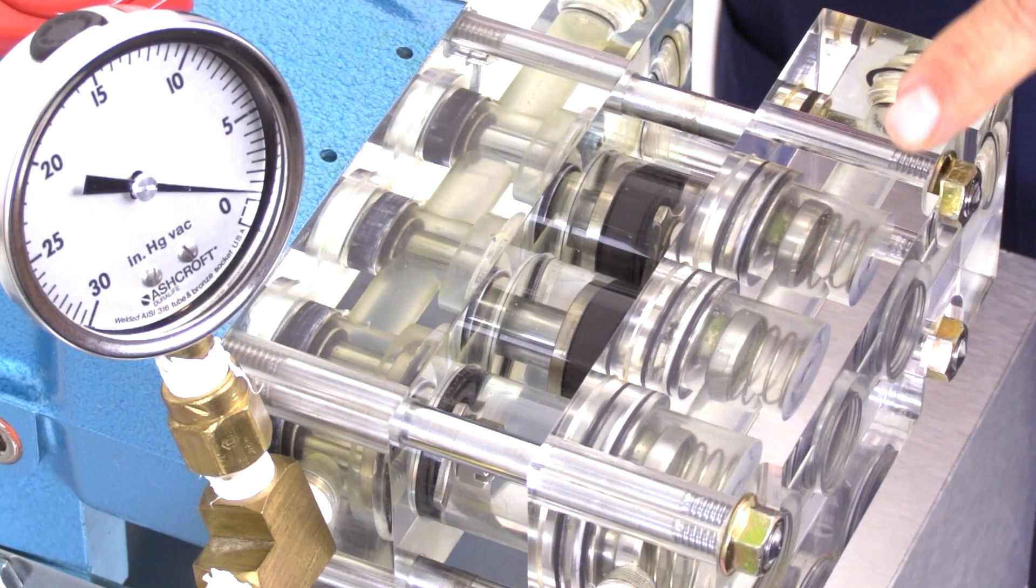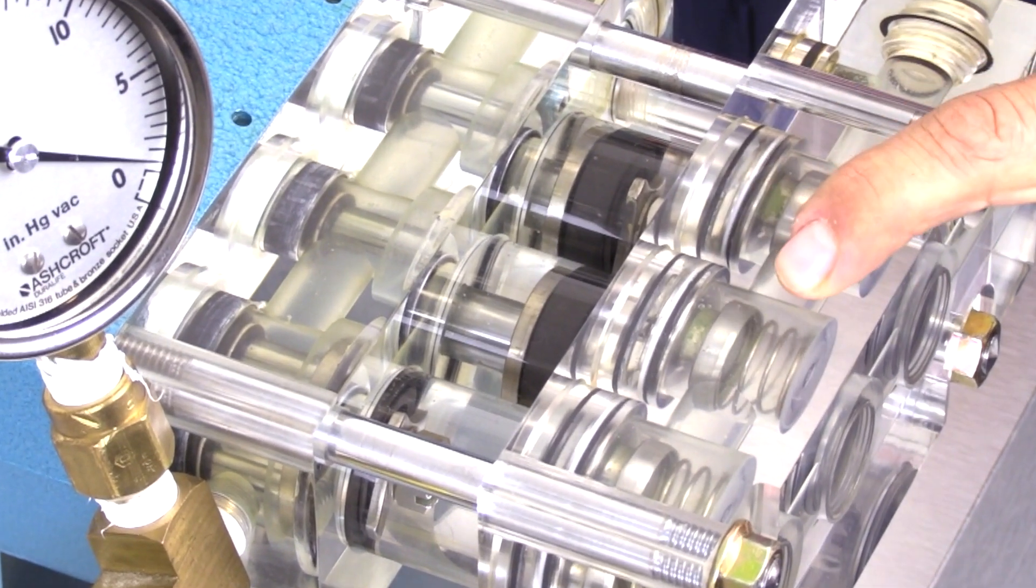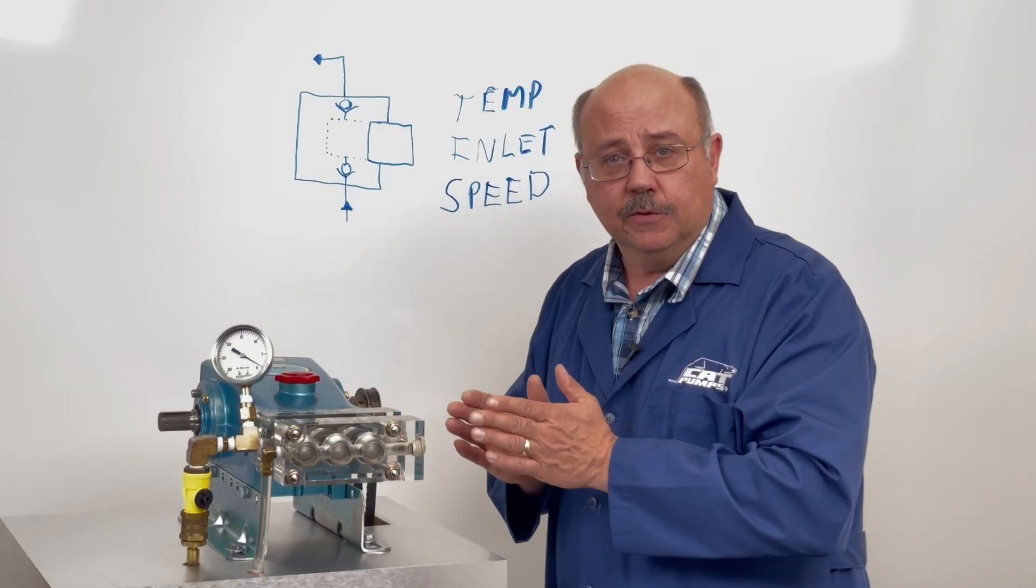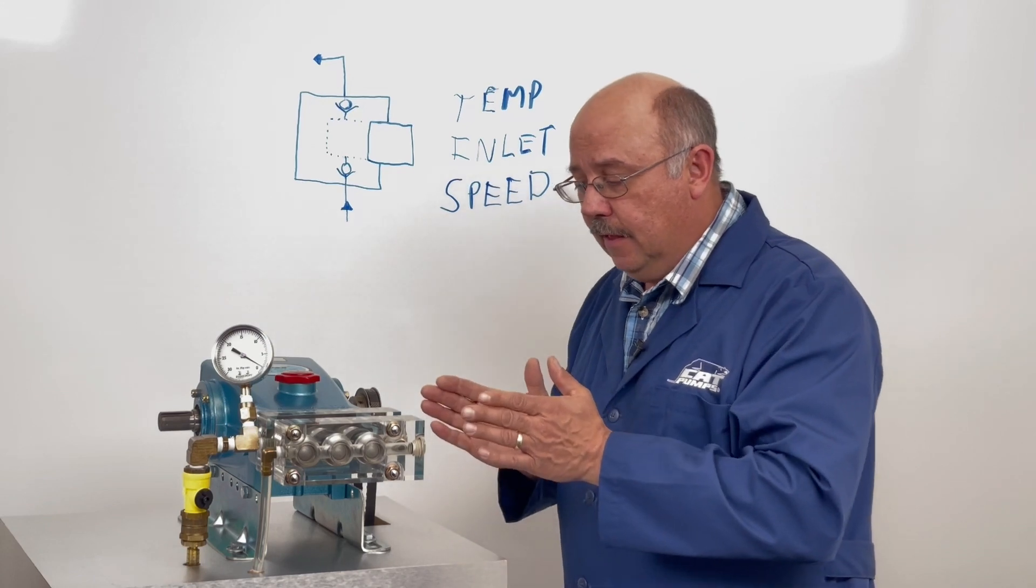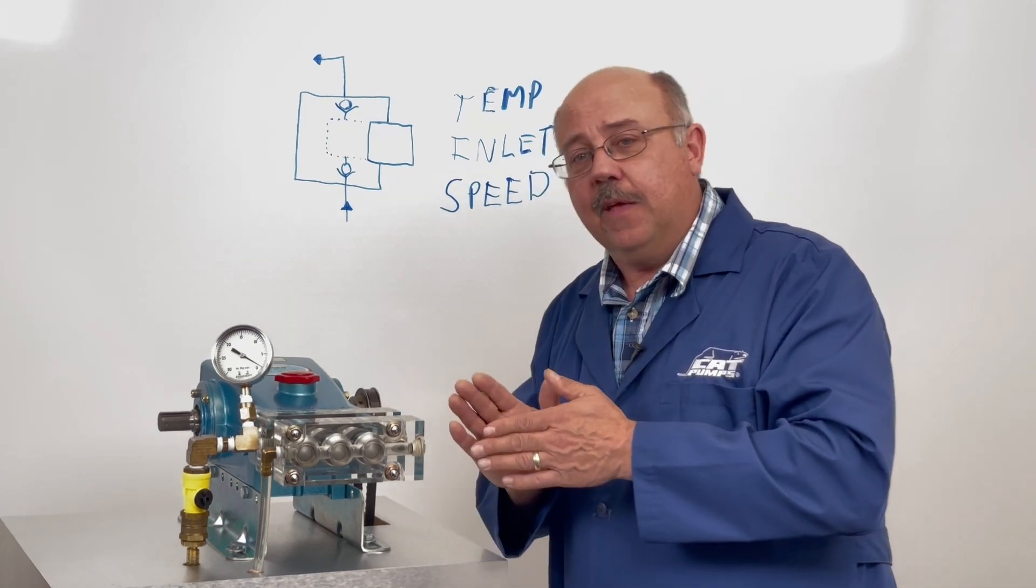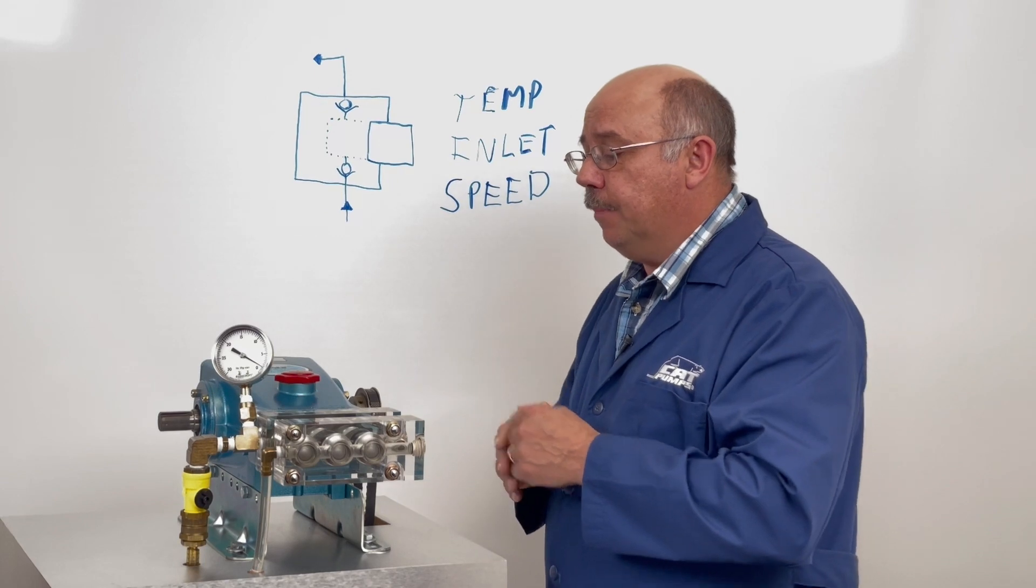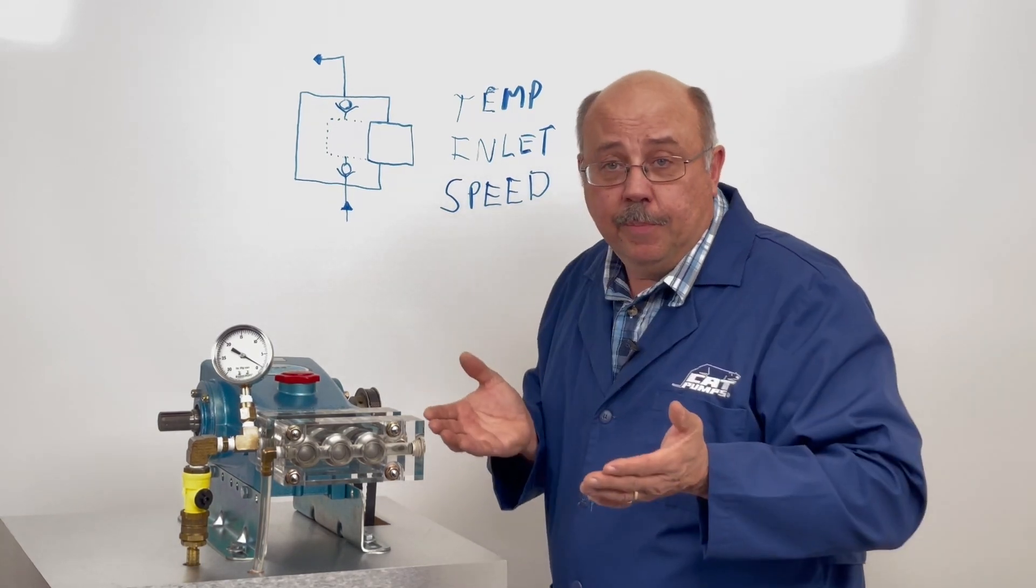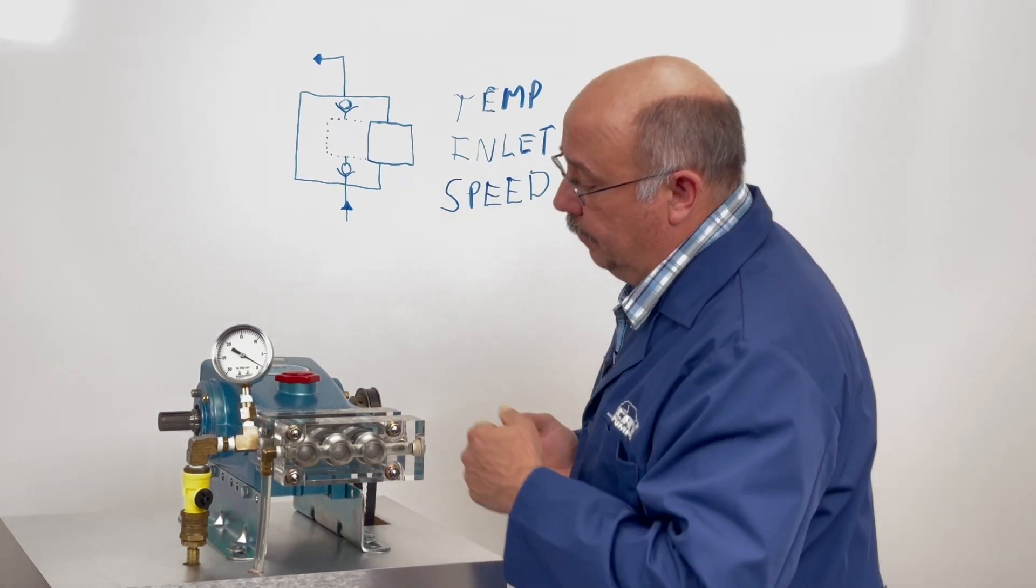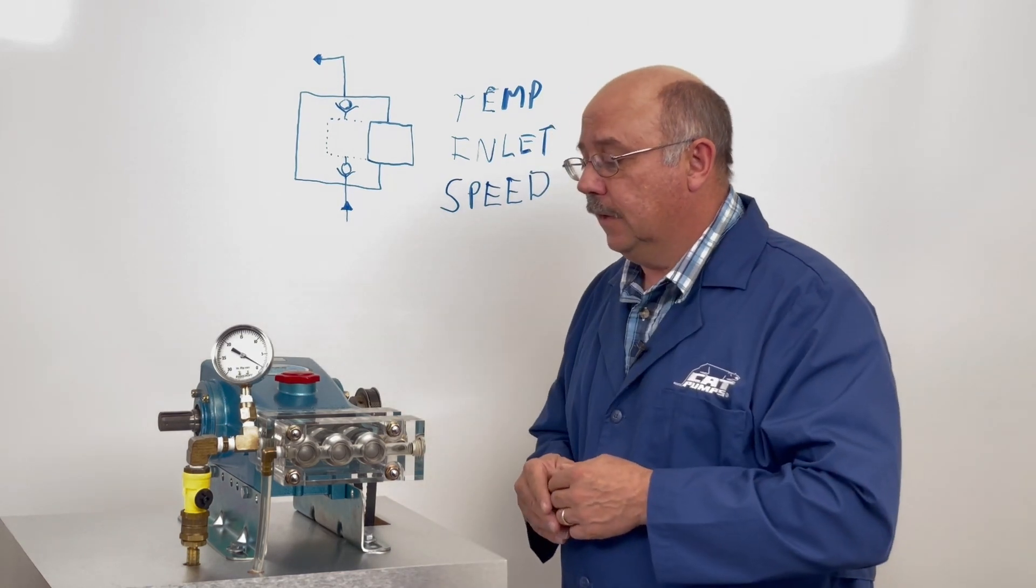And then there's a discharge valve assembly with a spring and a valve that's held closed by that spring. And then during the forward stroke that valve will come off enough to let that volume of water escape. And that's how the pump operates. And so we'll fire this up and get her going.